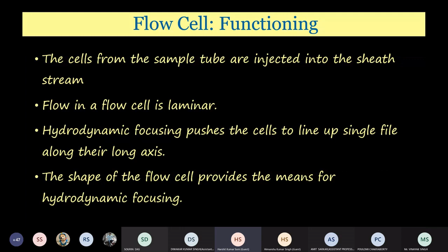So we will see the pressure differential. If the sheath fluid is at 10 psi and the flow cell is at 10.2 psi, you will see that only one cell is visible. If I increase it too much, to 10.8, you will see that the orifice is increased, and see the difference. So 4 cells are going, 1 cell is here, 2 cells, 4 cells. As you change the difference in pressure between the sample and sheath, the cell number will increase, and it will control the sample volume and flow rate. The greater the differential, the more the difference, the bigger or wider the sample core will be, and we will get more cells.